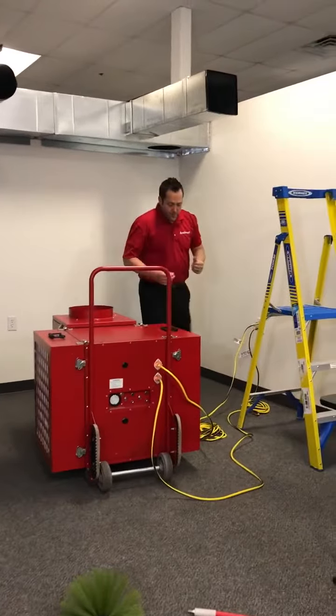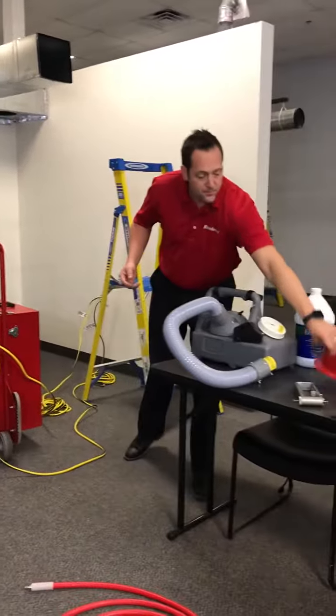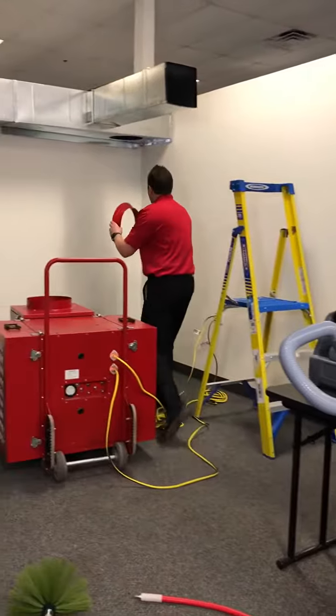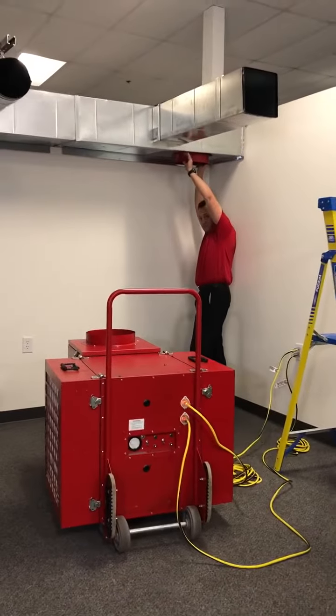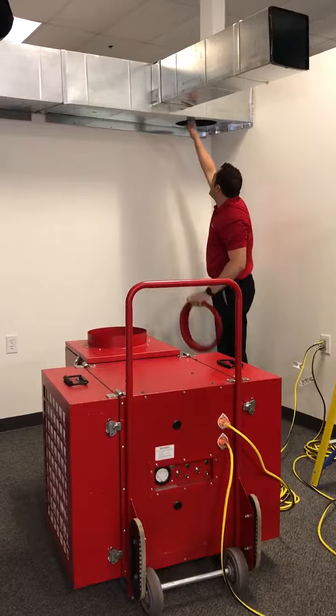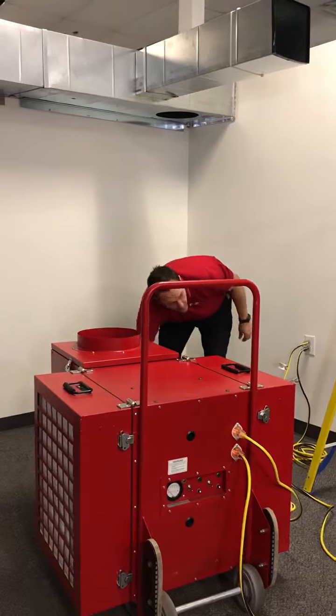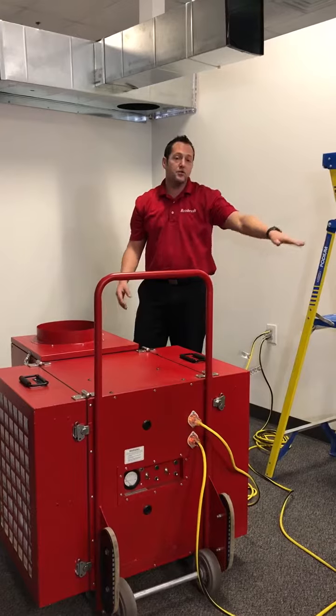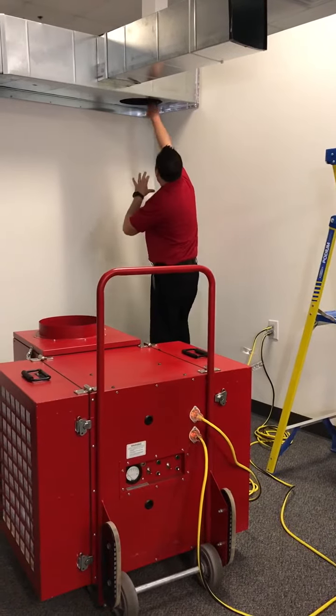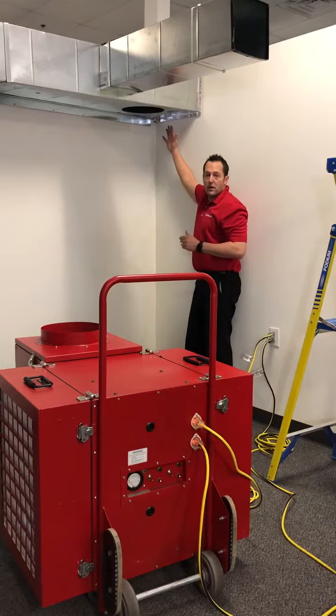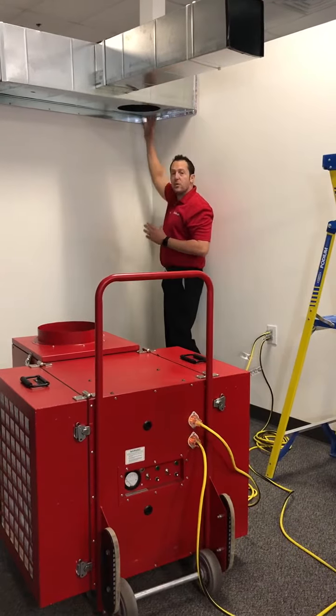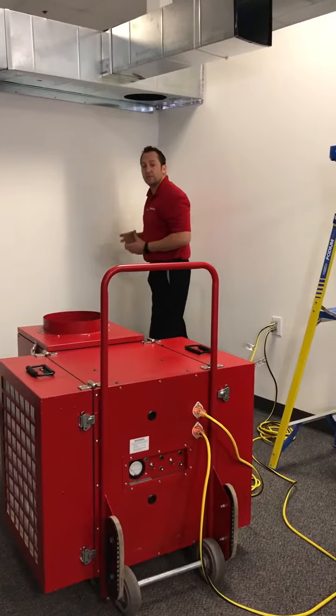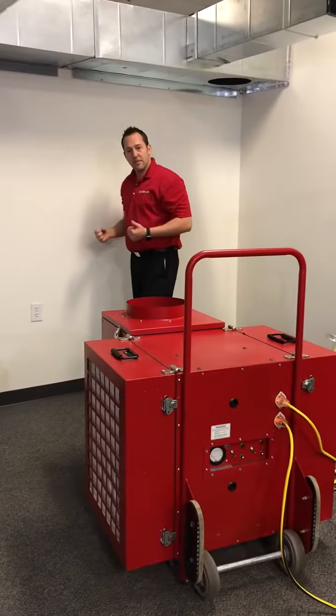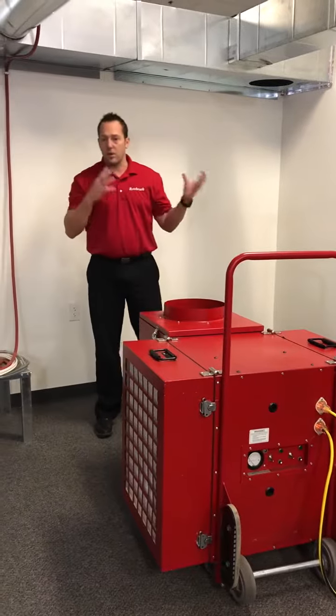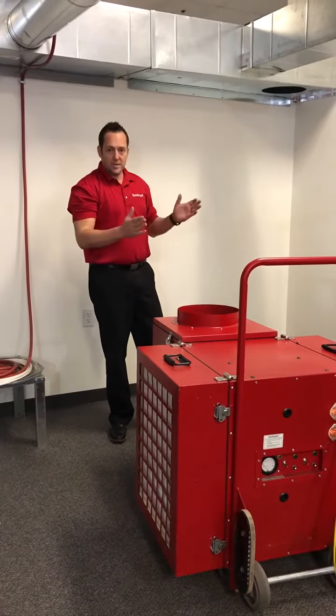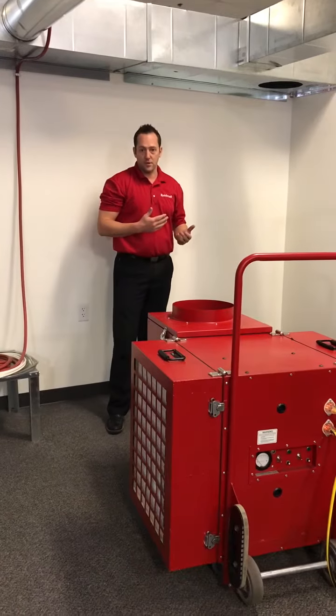Once you've done this, you're going to take the connector plate and attach it to the ductwork. Then you're going to take a zone bag, like we showed you here, whether it's the black or blue zone bag, and put it inside the hole to block off the air handler from the access point you've cut. The reason you're doing this is because all that dust and debris being sucked back to the air handler, as well as blowing it with dust and debris, will now be sealed off, ensuring it doesn't get on the actual unit itself.